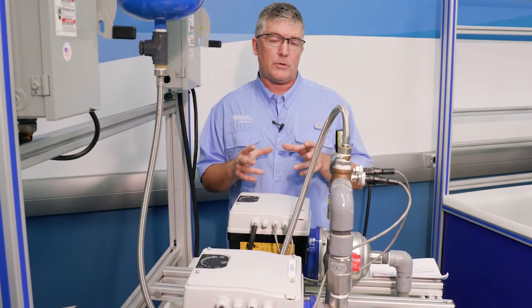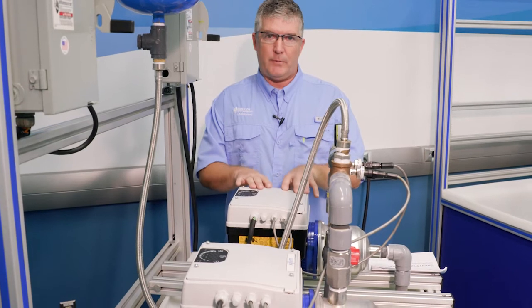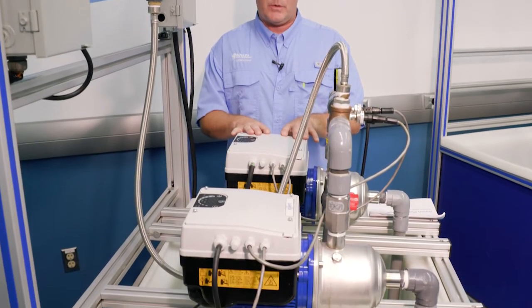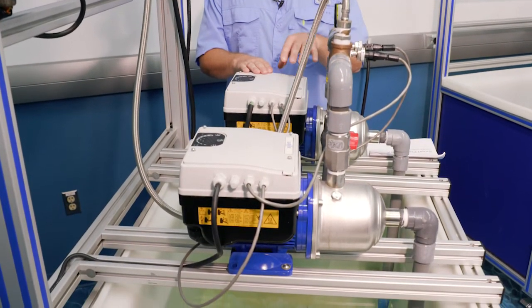Permanent magnet motors also require a drive. So with a permanent magnet motor, you have to have a drive like we can see here. The other thing about a permanent magnet motor is that it is a synchronous motor. So you're going to get a little bit more performance out of it, because more speed means more flow and more head.